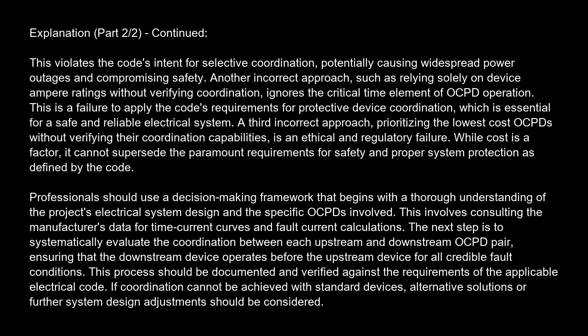This involves consulting the manufacturer's data for time-current curves and fault current calculations. The next step is to systematically evaluate the coordination between each upstream and downstream OCPD pair, ensuring that the downstream device operates before the upstream device for all credible fault conditions. This process should be documented and verified against the requirements of the applicable electrical code. If coordination cannot be achieved with standard devices, alternative solutions or further system design adjustments should be considered.